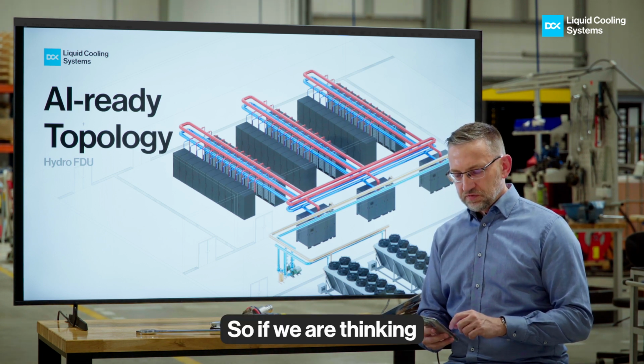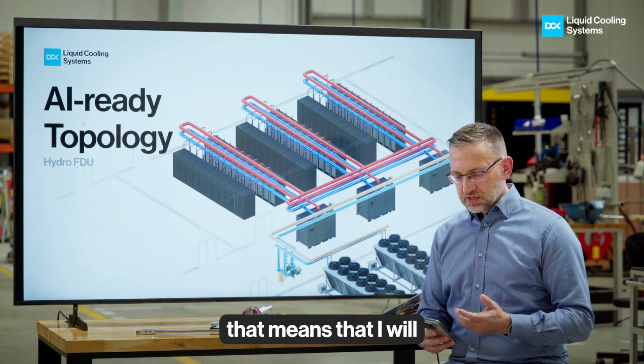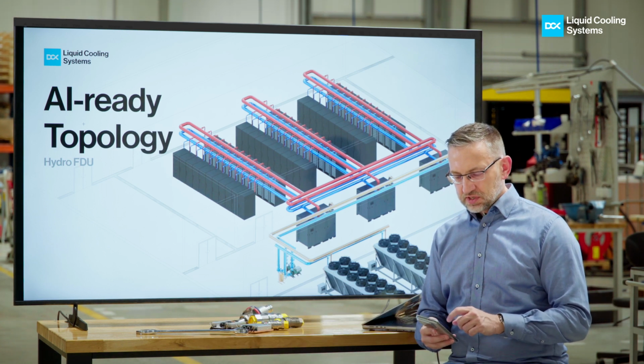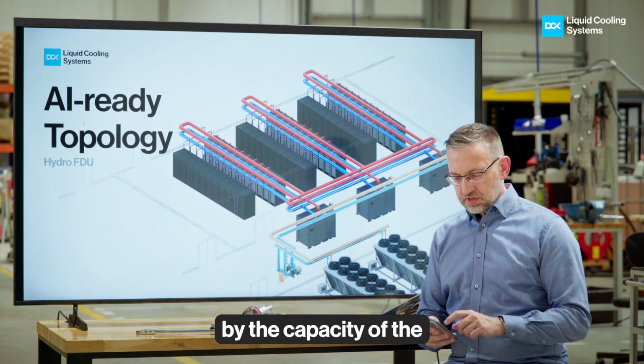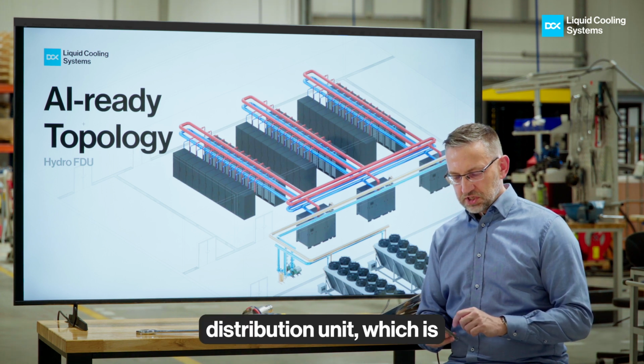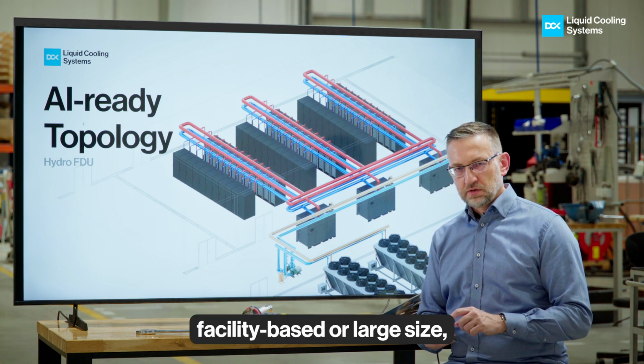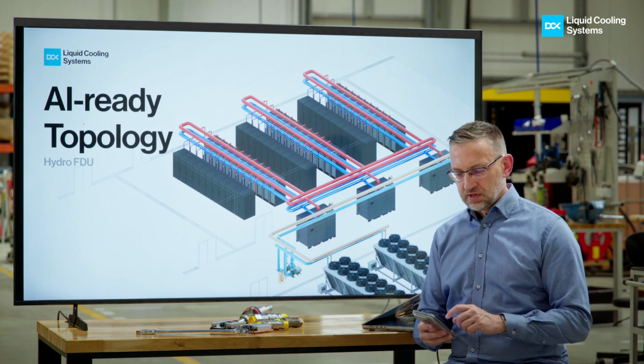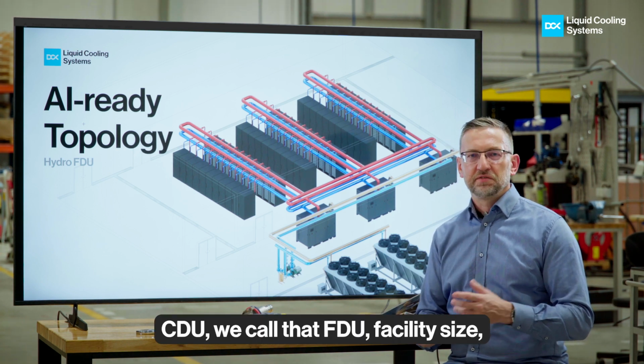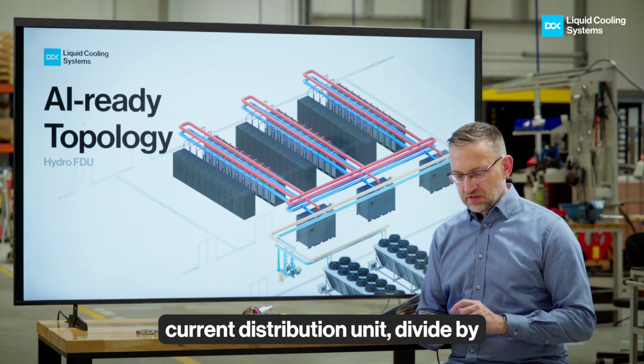So if we are thinking about the 6 megawatts, that means I will divide that 6 megawatts by the capacity of the coolant distribution unit, which is facility-based or large size CDU. We call that FDU, facility size coolant distribution unit. Divide by 5.